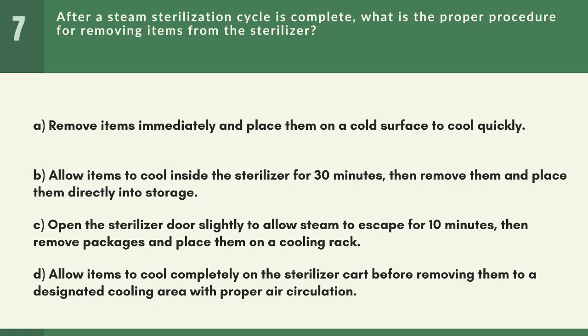Question 7. After a steam sterilization cycle is complete, what is the proper procedure for removing items from the sterilizer? A. Remove items immediately and place them on a cold surface to cool quickly. B. Allow items to cool inside the sterilizer for 30 minutes, then remove them and place them directly into storage. C. Open the sterilizer door slightly to allow steam to escape for 10 minutes, then remove packages and place them on a cooling rack. D. Allow items to cool completely on the sterilizer cart before removing them to a designated cooling area with proper air circulation.